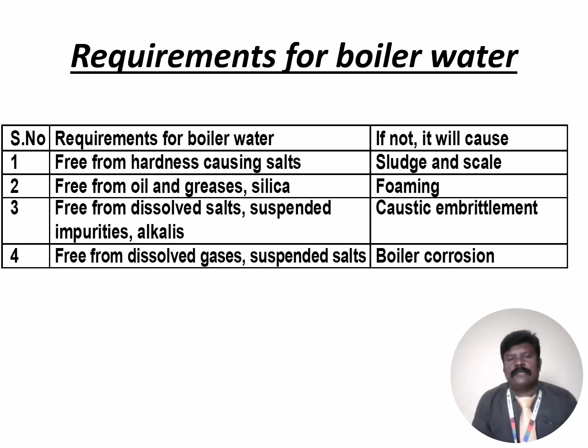Let me see first scale and sludge formation. If the water contains hardness causing salts like magnesium sulfate, magnesium chloride, calcium carbonate, magnesium carbonate, calcium sulfate, calcium bicarbonate, on evaporation, the salts are precipitated. If the precipitate is in the form of slimy, non-adherent precipitate inside of the boiler, it is known as sludge. If they form a very hard, thick, strongly adherent coating between the boiler wall and the water, that material is known as scale.